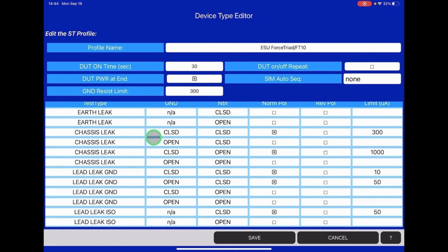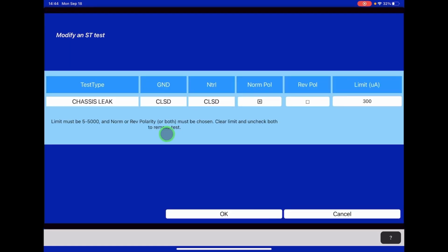Per the manual, we could either run a chassis leakage test or an earth leakage test. We're going to go ahead and program it to do a chassis leakage test or an enclosure leakage test. Once we've selected that, we need to do it in normal conditions, which is with the ground closed, the neutral closed, in normal polarity. We're not going to run it in reverse polarity. And we've set the limit to 300 microamps, which is what's stated in the service manual.